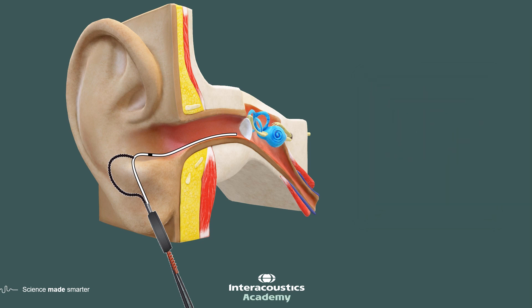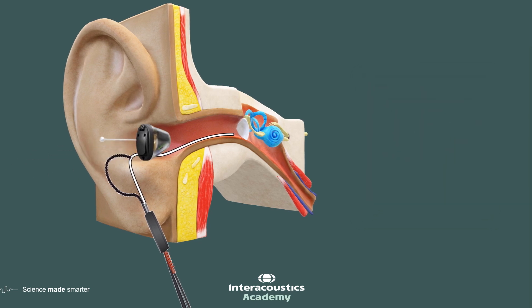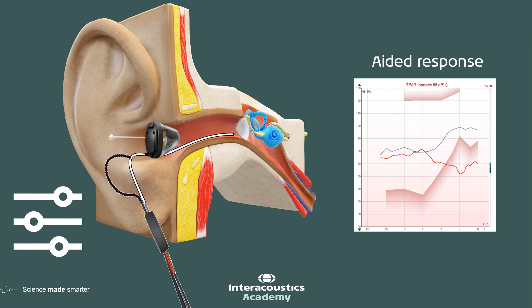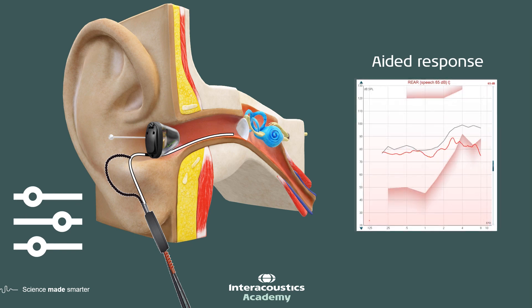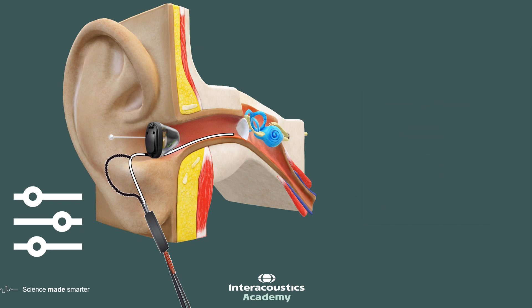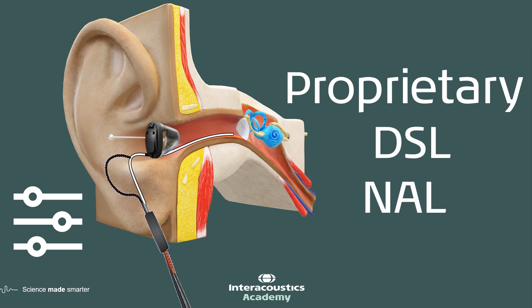We can then place a hearing aid in the ear canal and play that same sound again, measuring the response at the eardrum with the probe microphone — now we have an aided response. That aided response can then be adjusted in the hearing aid fitting software to bring it closer to the target. The target is the grey line shown on screen, and the red line is the aided response. That target is defined by the prescription formula chosen — we could use a proprietary formula, DSL, or NAL. However, the decision-making process around choosing these is outside the scope of this lecture.